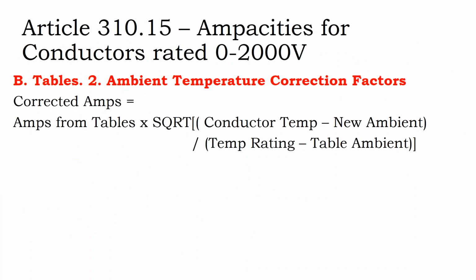And so what you might say, well, what's the difference? Well, actually, when you're calculating the internal temperature of that wire, you have to look at your ambient temperature and the amount of amperage that's going through it. An engineer would come in and make a more exact calculation, whereas the tables are saying this is for an environment that's going all the way up to 86 degrees ambient. This is for an environment that's going all the way up to 104 degrees ambient. And so it's being conservative on your wire sizing for that electrician who is not actually performing the actual temperature calculation. And so here's our actual temperature calculation that an engineer could use.